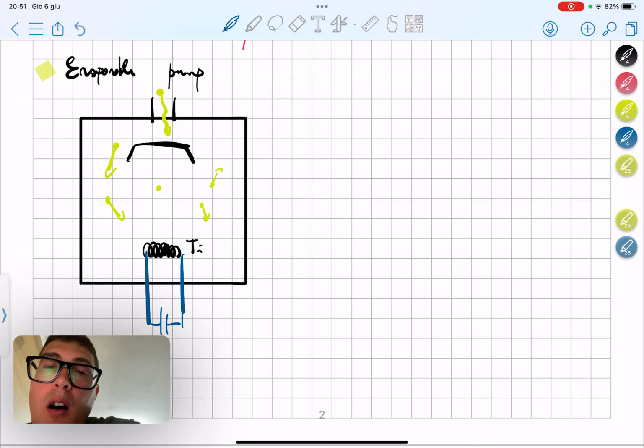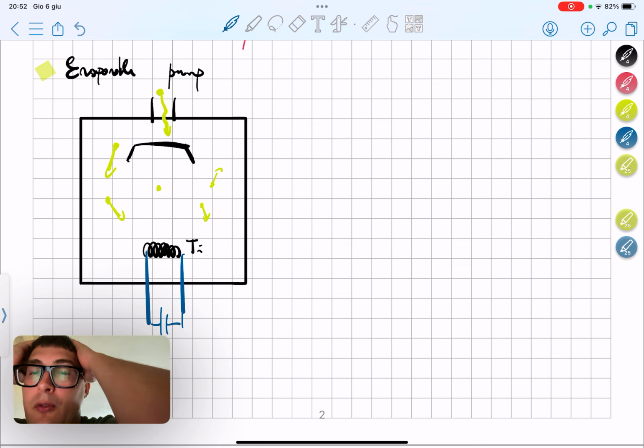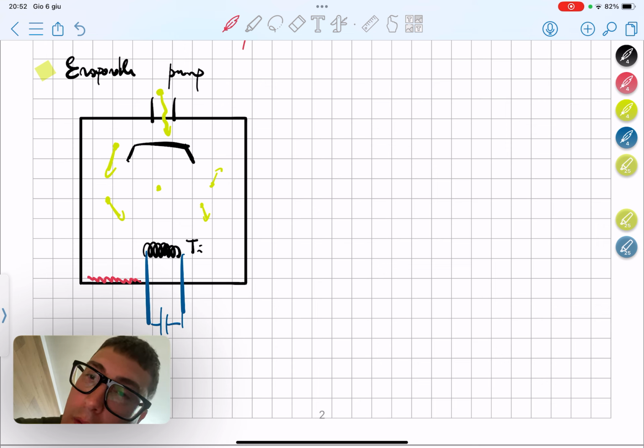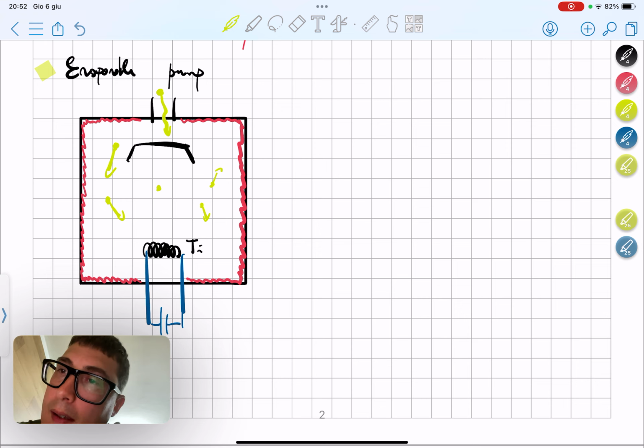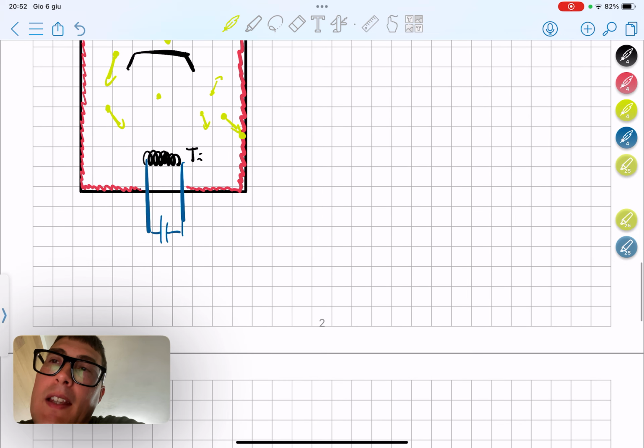So essentially, the working principle is that by applying a difference of potential, we will create a current. The current will increase the temperature of the filament, which will sublime, passing through a phase transition from solid into gas, and it will release titanium ions that will essentially create a cover, onto which is spanning the surface of the interior of the pump, and this cover will make the atoms of the molecules become trapped, become absorbed by the surface, and in this way they will be effectively reducing the gases by absorbing and keeping them inside the pump.